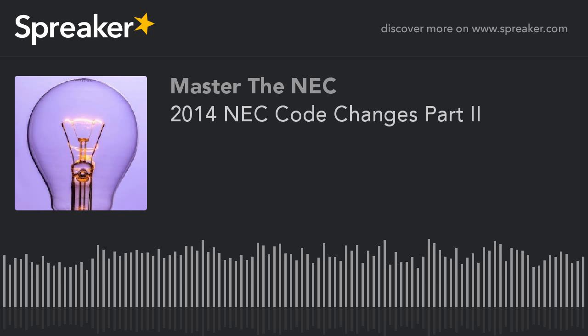Again, they added the "or devices" in there, but what was new here is we're talking about a listed branch circuit type AFCI back at the panel and having an OBC, which is basically an outlet branch circuit AFCI device, at the first receptacle. So this is going to permit you to do that, and I could do it in type NM cable. It wouldn't have to be in MC or rigid. I could do that as long as I put a branch feeder type AFCI in the panel, and then I put an OBC at the first receptacle.